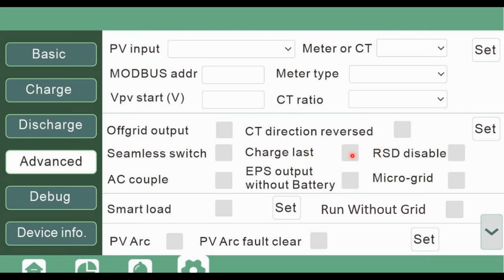When enabling rapid shutdown disable, you basically enable this when you're using systems with AC coupling, where the microinverters themselves have their own RSD functionality, right? So you would need that here. AC coupling: when enabling AC coupling, this is how you would enable it. And then, as talked about before, the charge setting is where you would program it to work when desired.